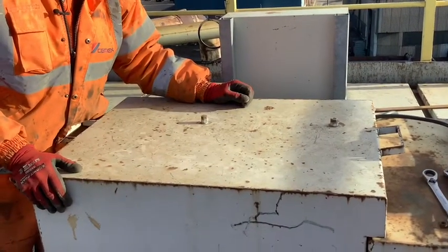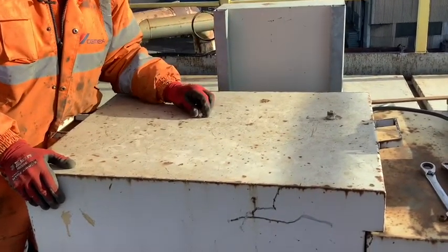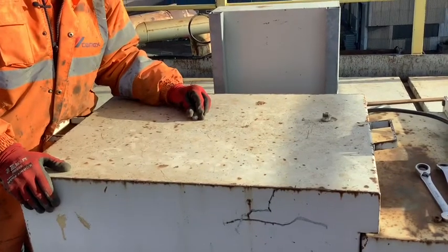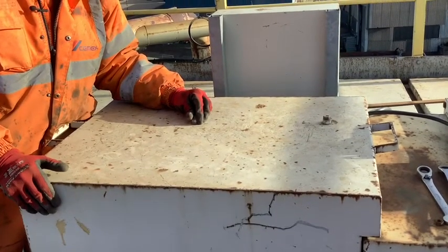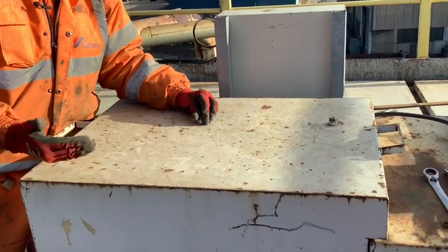In this example, you can see the free clean mechanism, the cone, is trying to split between 2 compartments and therefore is not cleaning correctly or applying the maximum amount of force in order to clean the bags. This results in a lack of extraction and a possible failure of the system. As with all guards, to protect from moving equipment, we must ensure that the nuts are tool tight. Please look at your system to make sure you're not using wing nuts that could be hand tight.